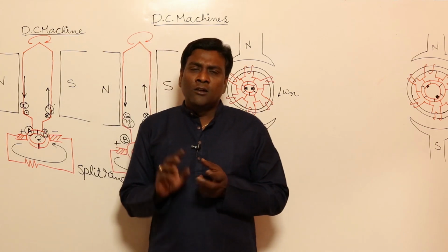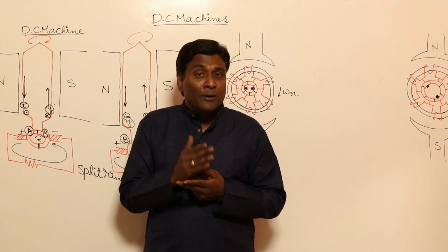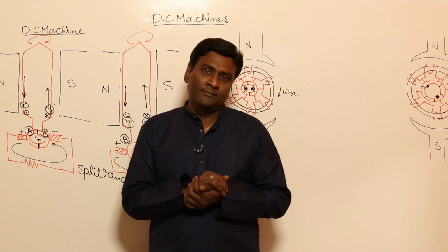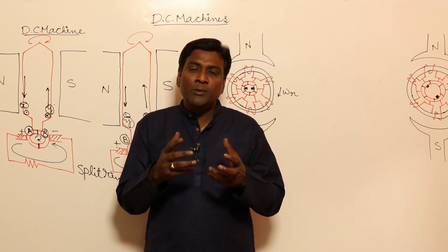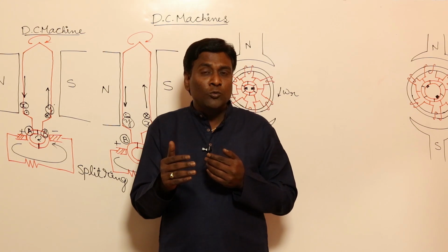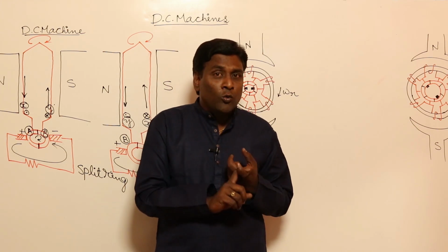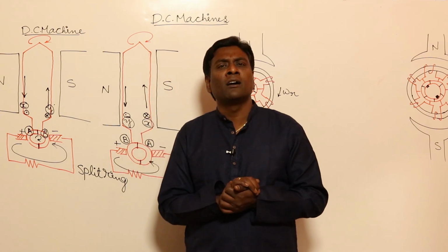In our synchronous machines we have seen, is it better to keep the armature in the stator or rotor? Stator. Because if you think of the rotor, mechanical stress will be more because of centrifugal forces. The moment mechanical stress is more, you cannot use low quality insulation; rather hard composition materials like asbestos, mica and PVC have to be used.